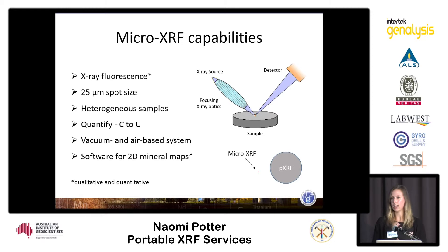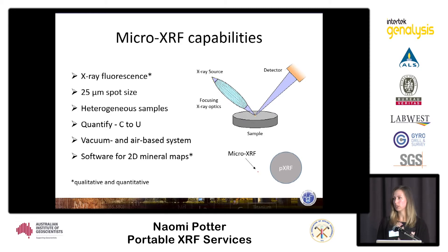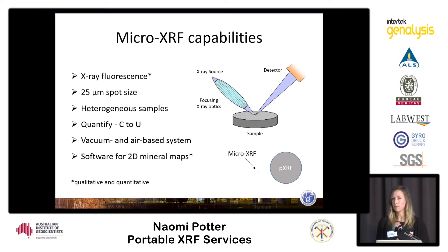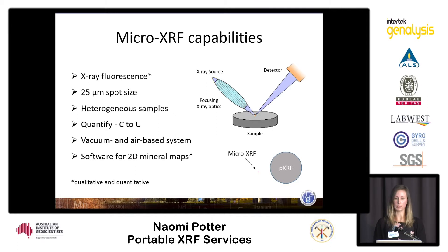The ability to analyze heterogeneous samples, because of that small spot size, is enabled by the use of fundamental parameters. So rather than using a standard-based system, you're using mathematical algorithms to determine the chemistry. The quantification can go from carbon to uranium. It's able to measure those lighter elements below sodium because it has a vacuum-based system, so it can pick up the energy released from those lighter elements.